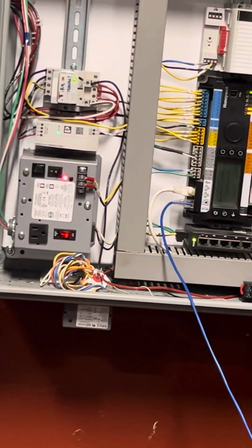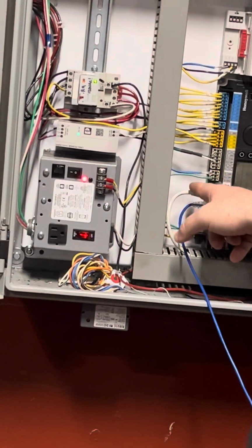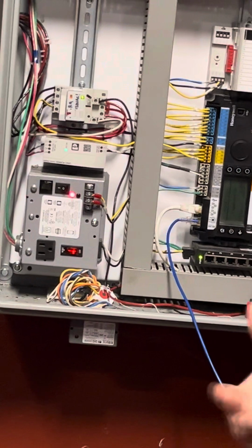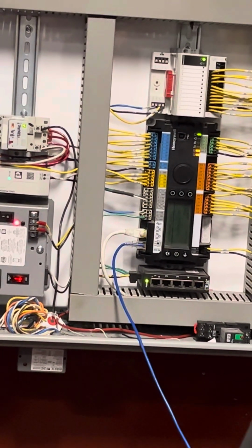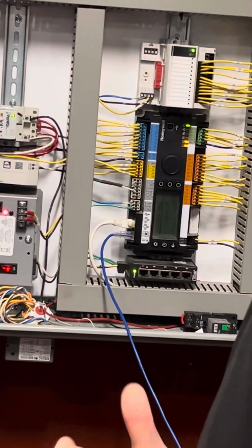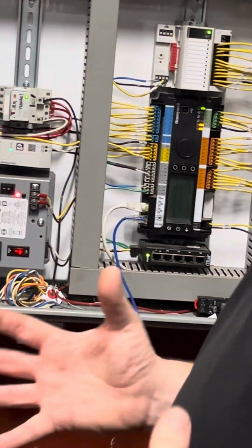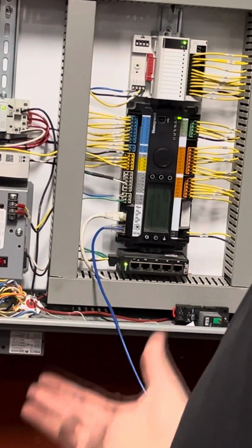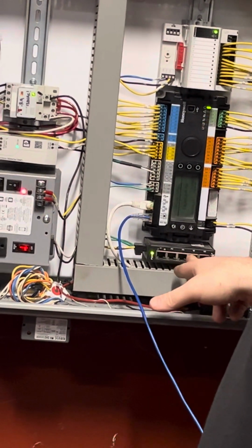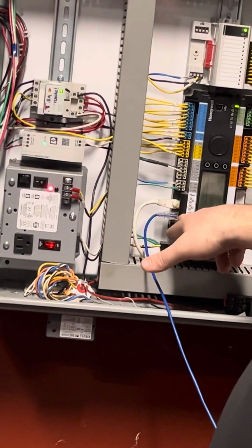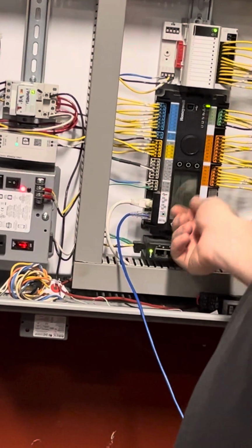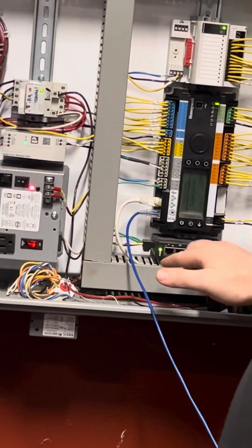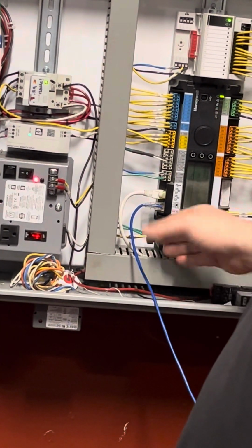In theory, what should have happened, the school's network should have come into here and then come out to here. Or what we can do in the future, if we needed to do something like a BACnet IP integration, we can, without having to tie it into the school's network, a third-party device. I can give it whatever IP address I need, bring it into this extra port that's right here that I'm plugged into, and then if I have to come in and still connect to this, I can plug into this. There's 100 different ways. Nothing's plugged into it, it's not being used, it's just powered on.